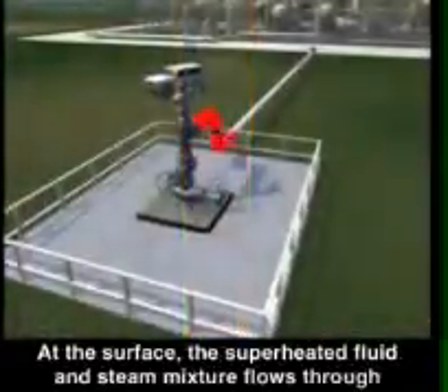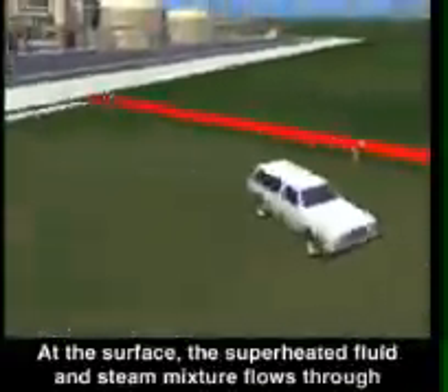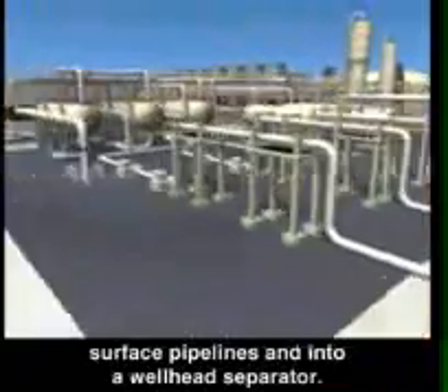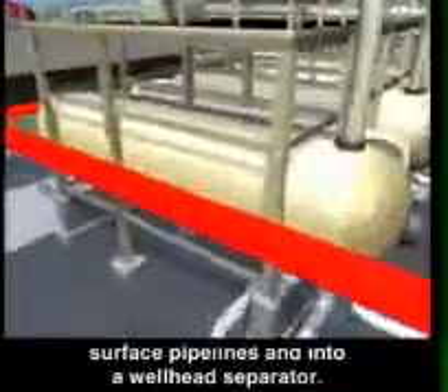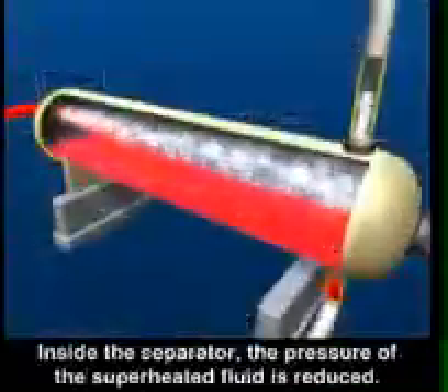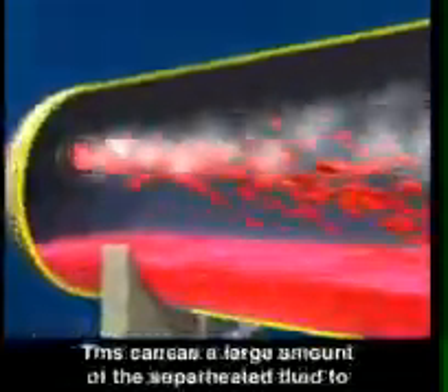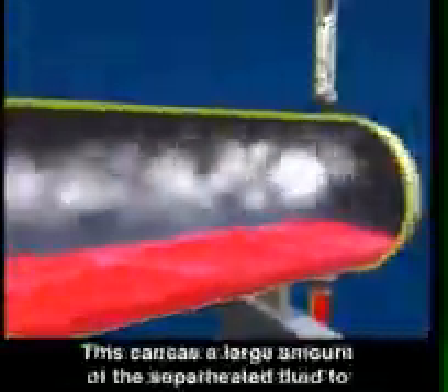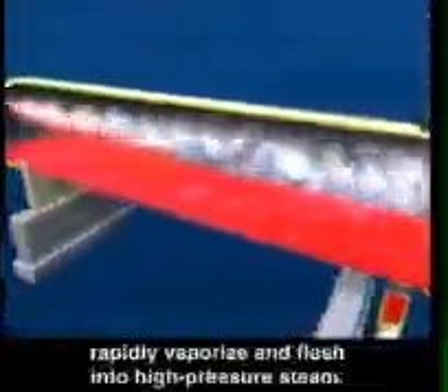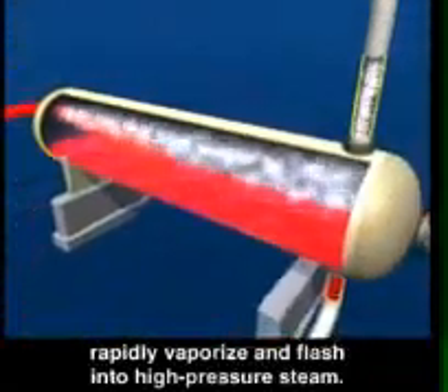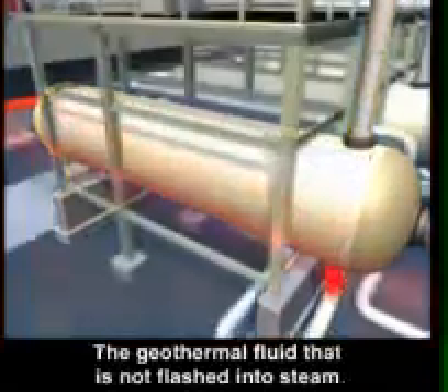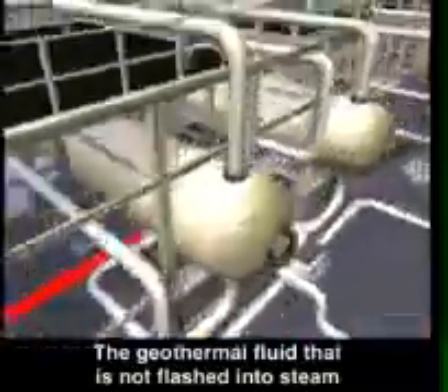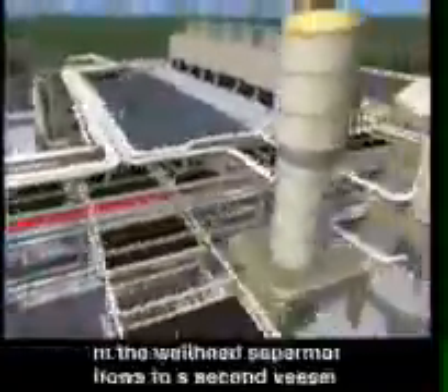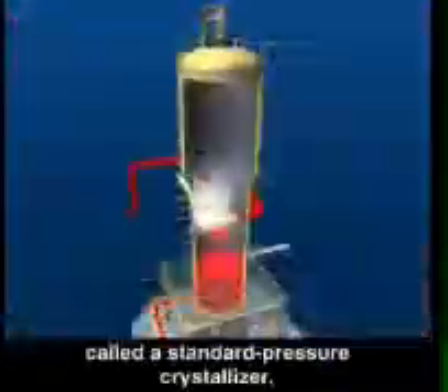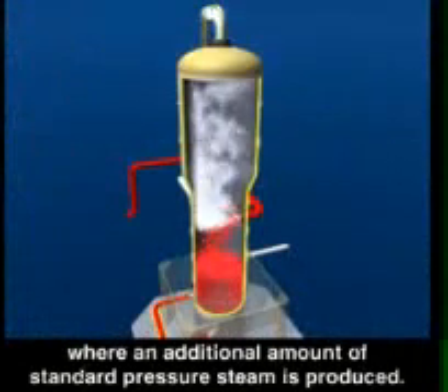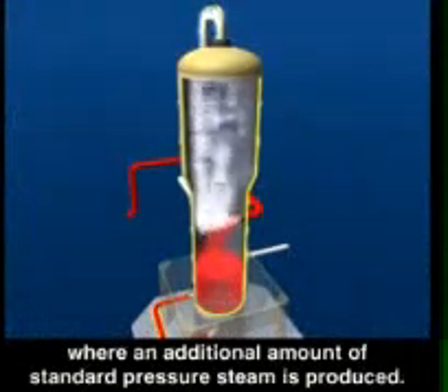At the surface, the superheated fluid and steam mixture flows through surface pipelines and into a wellhead separator. Inside the separator, the pressure of the superheated fluid is reduced. This causes a large amount of the superheated fluid to rapidly vaporize and flash into high-pressure steam. The geothermal fluid that is not flashed into steam in the wellhead separator flows to a second vessel called a standard pressure crystallizer, where an additional amount of standard pressure steam is produced.